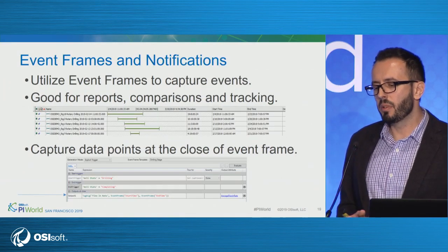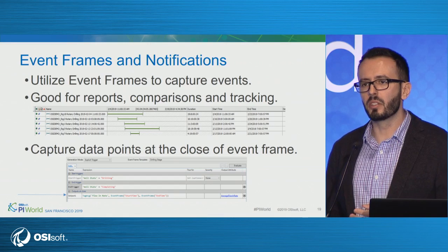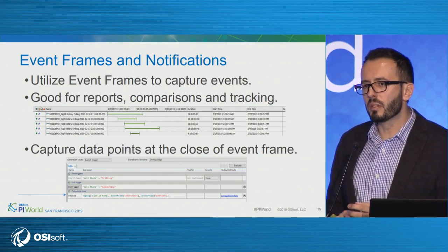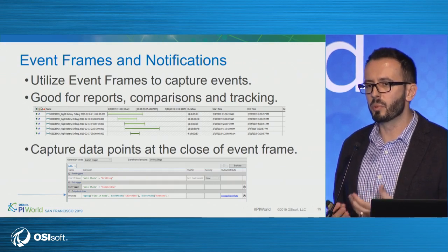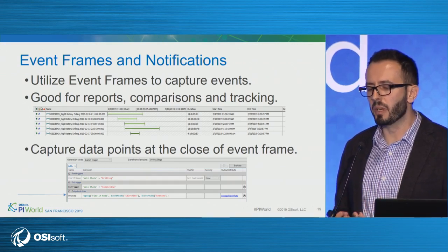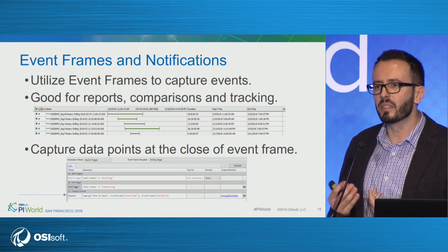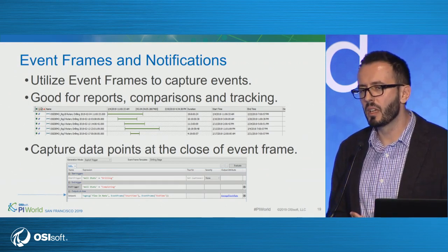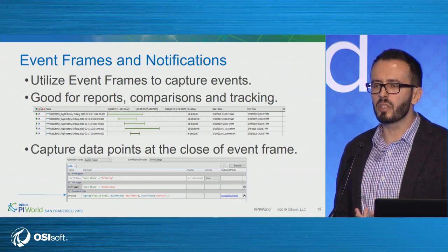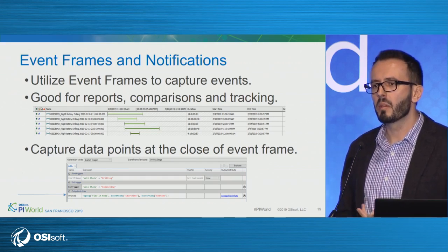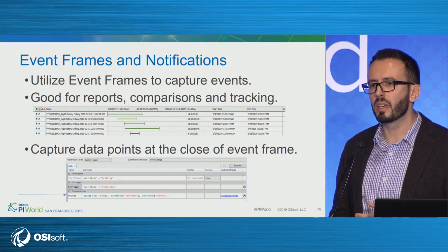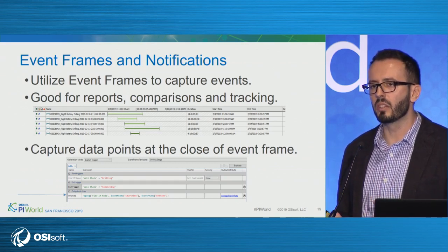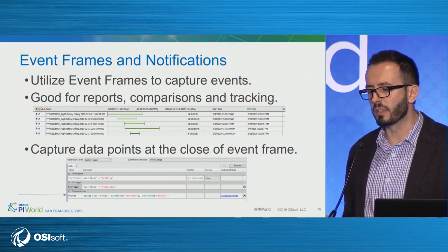Let's speak a little bit about event frames and notifications. Event frames, the basics of it, are some important events captured for you in a database that have a start time and an end time. They're really good for reports, comparisons, and tracking. You can utilize the calculations to generate event frames based on some start triggers and end triggers. So you can define when you want to start an event frame and when that event frame should end.